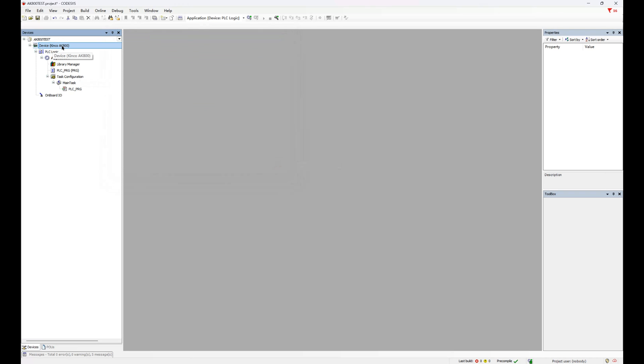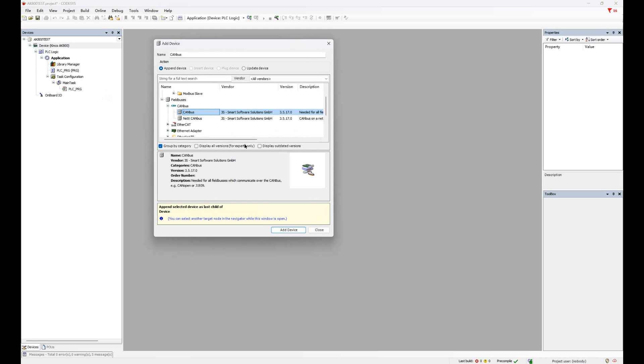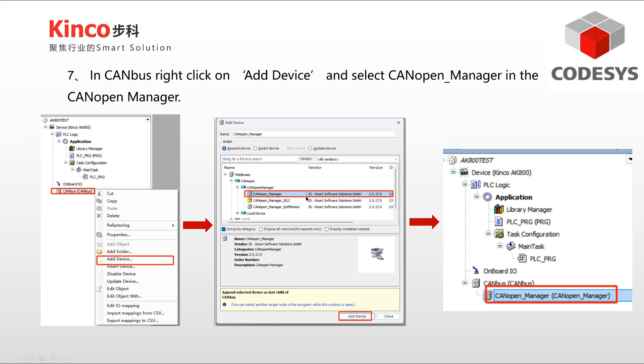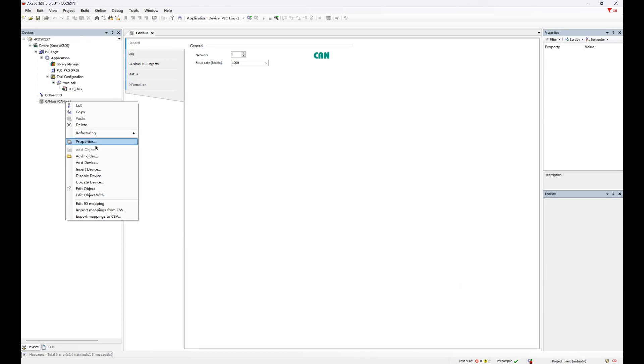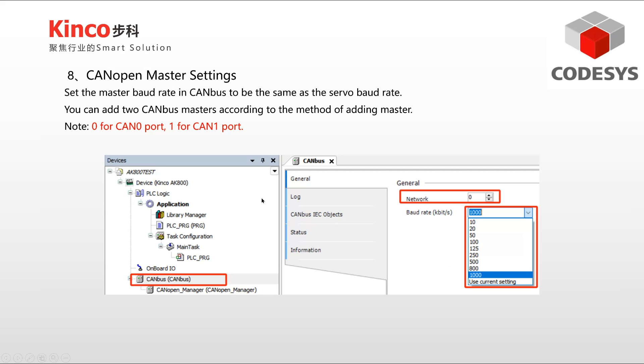Right-click the AK800 and add the CAN bus, then add the CANOPEN manager in the same way. Next, set the CANOPEN master parameters and baud rate. Note that the AK800 supports both CANOPEN and EtherCAT. You can choose EtherCAT, which has higher synchronization accuracy than CANOPEN.